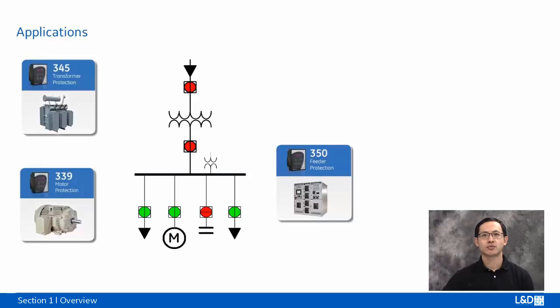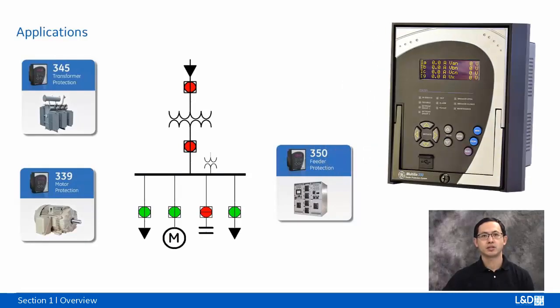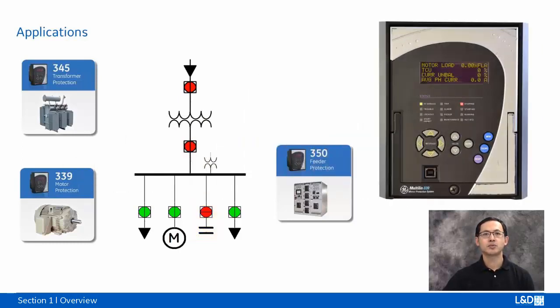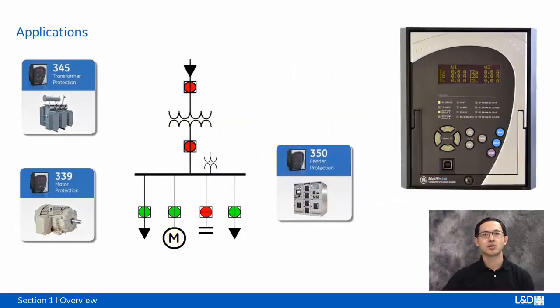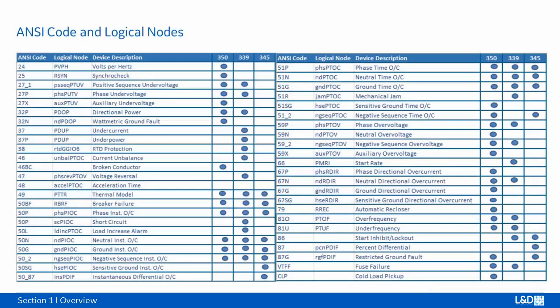There are 3 types of 3 series relays. The 350 is used for feeder protection in medium voltage and high voltage, utility and industrial. It can be changed to a voltage relay by changing the order code, and it can also be used for capacitor bank protection. The 339 is used for the protection of low voltage and medium voltage motors of various sizes. The 345 is used for the protection of 2-winding power transformers, reactors, and auto transformers. This is summarized in this comparison table.